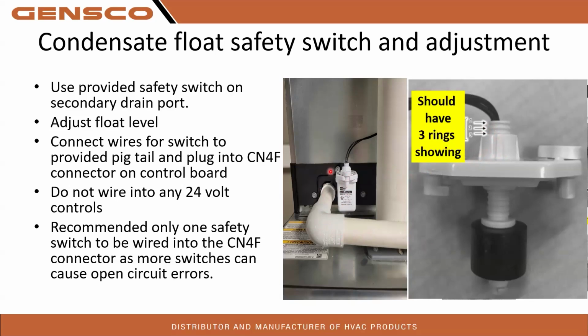Once you get that installed, in your kit comes a pigtail for the CN4F connector. It's got a gray and a white wire attached to it. That is for your safety switch. So what you're going to do is wire nut this safety switch to that pigtail. It plugs into CN4F on the board, which I'll show you here in a little bit.